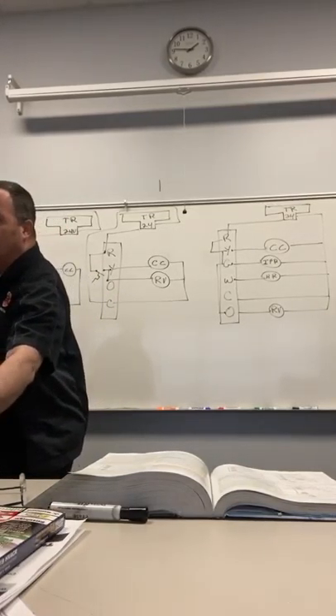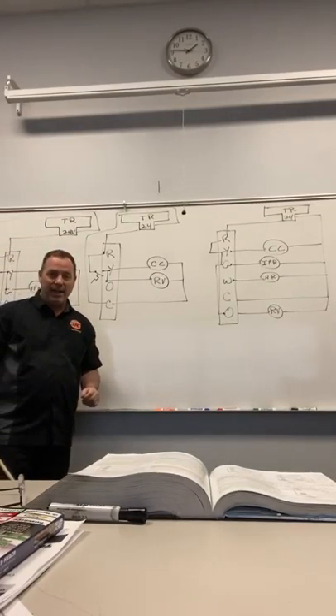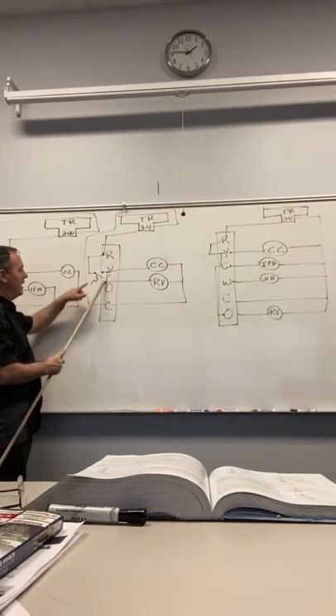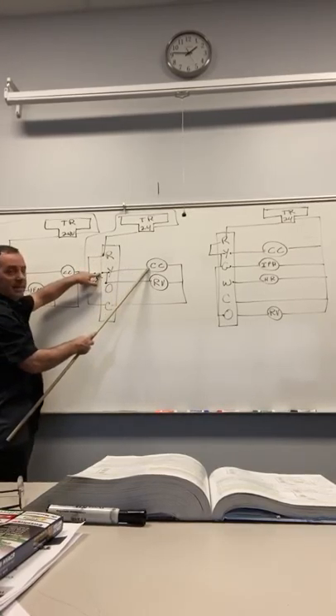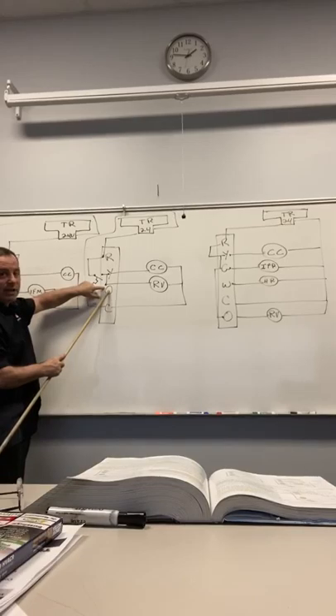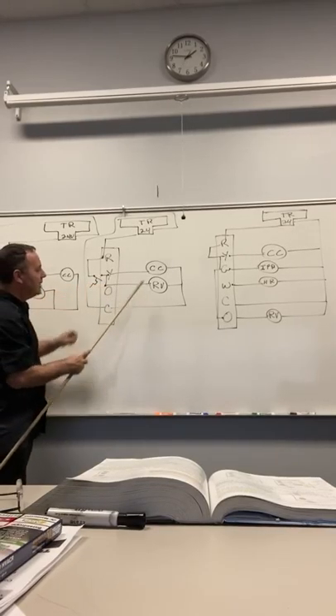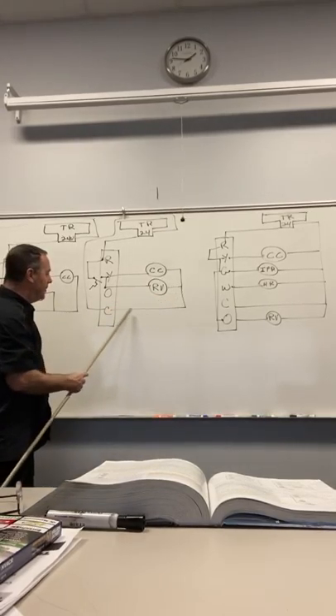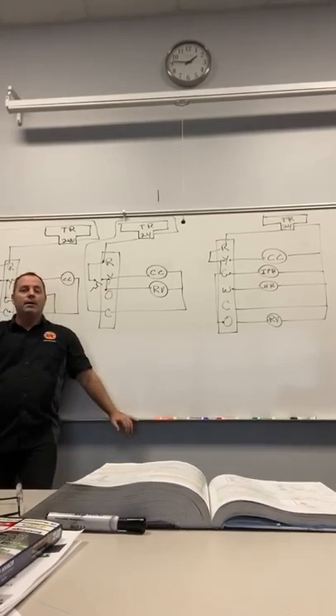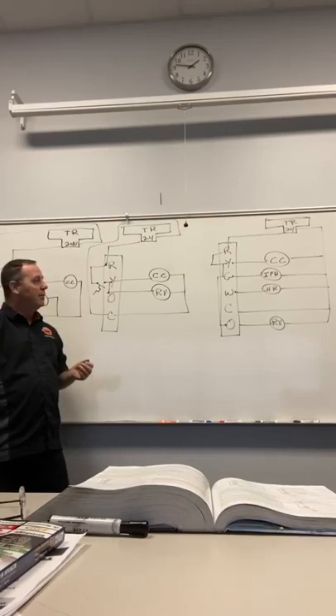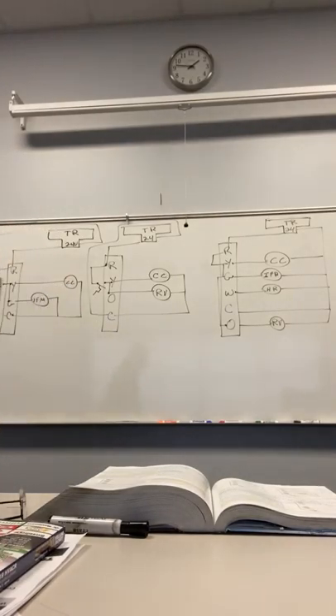Next. Here, I took that fan circuit out and drew in a reversing valve for a heat pump. Remember, a reversing valve in a heat pump is energized during cooling mode, not heating mode. So, R now sends power when this makes, and this closes to my contactor coil. So, my indoor fan, G, and O is energized, which is an orange wire. And that connects to my load here, which is my reversing valve outside, and then they come back to common. That's how that's connected.